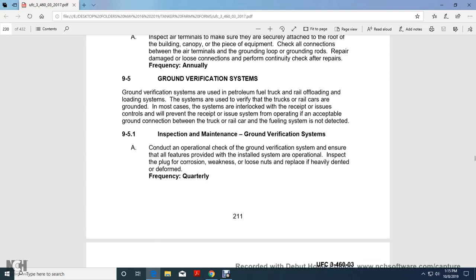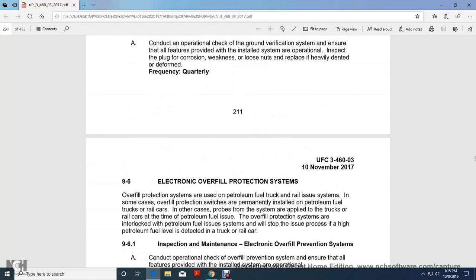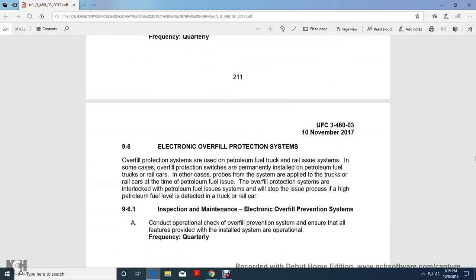Inspection and maintenance of the ground verification system. Conduct an operational check of the ground verification system. Ensure that all the features provided with the installed system are operational. Inspect the plug for corrosion, weakness, and loose nuts. Replace it if heavily dented or deformed, quarterly.